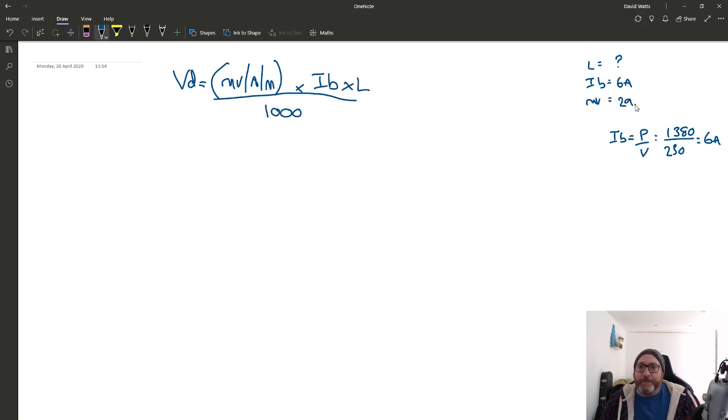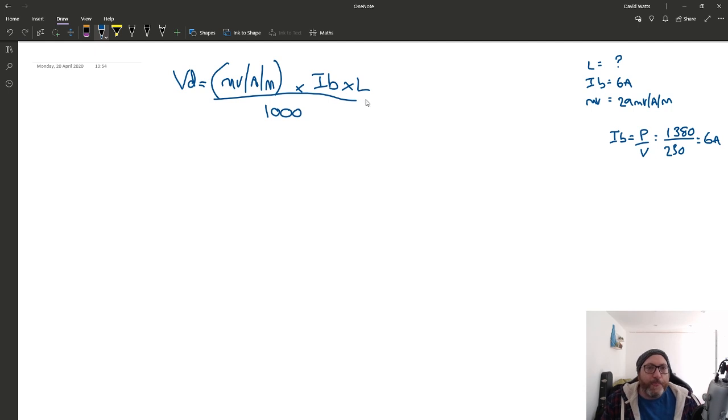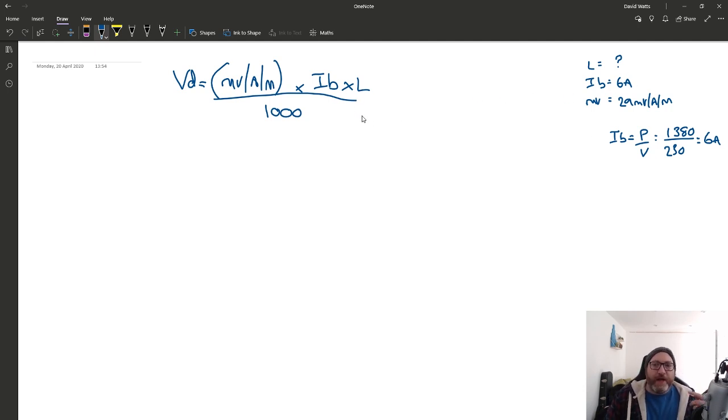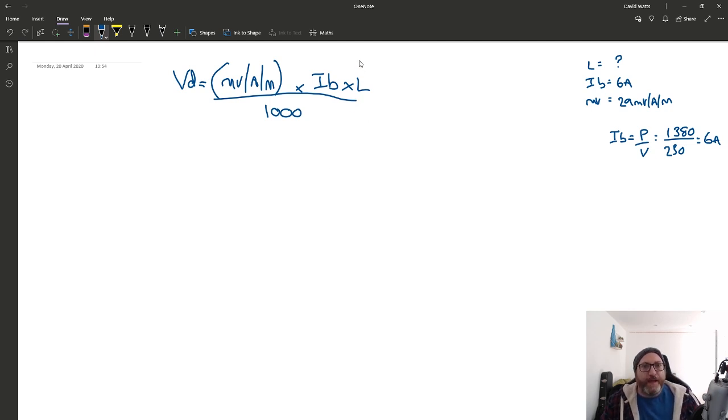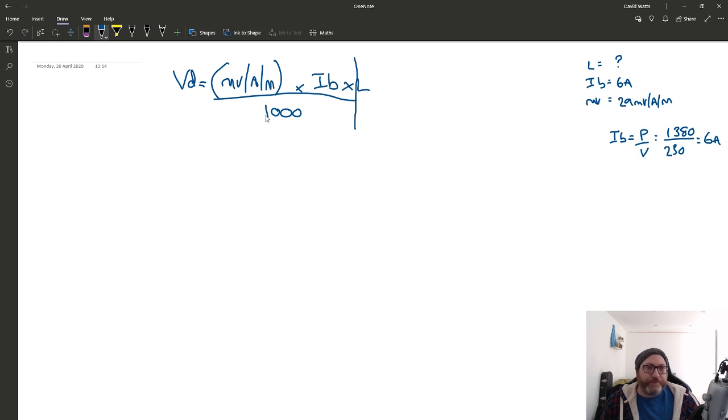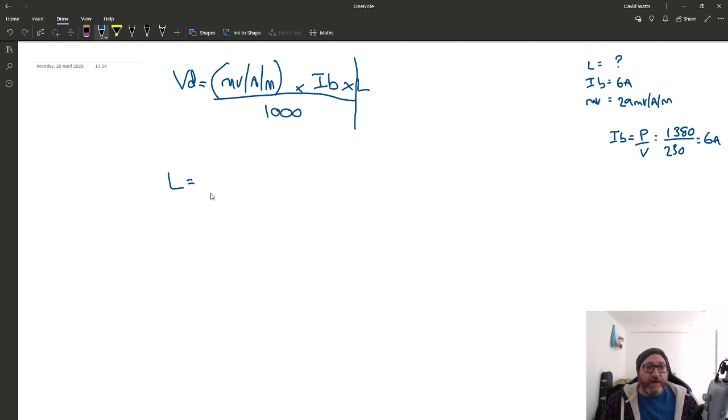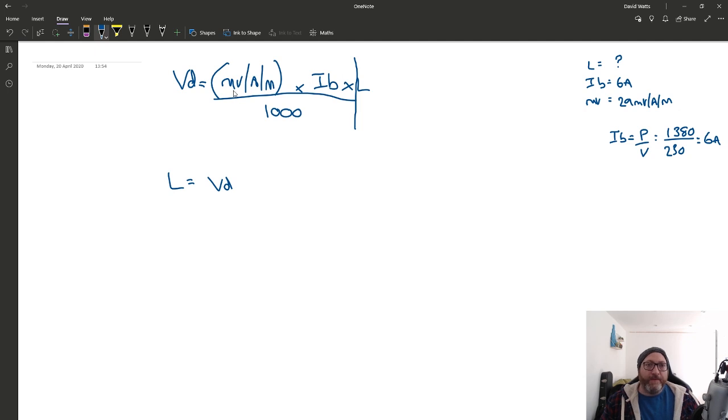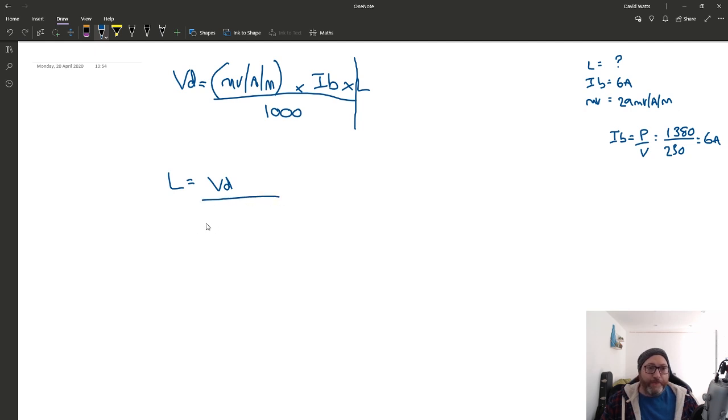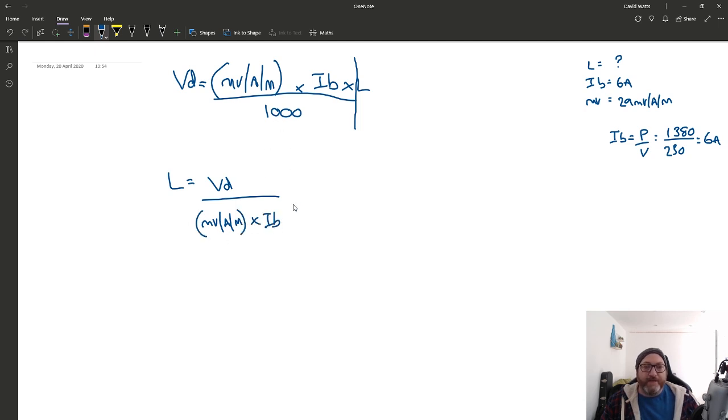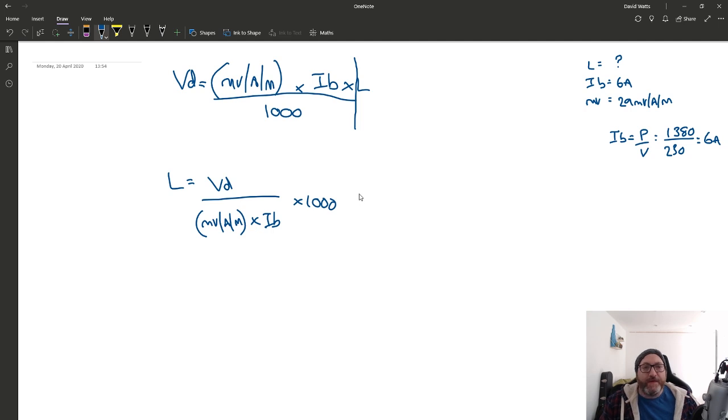Now we've got some information. Now we can start working things out. But first, the question is asking you what's length. So, this is where it talks about transposition of the formula. So, what you need to remember with that is take the thing that you want to take, the length here, and everything else the other side of that you need to bring this way, flipping it around. So, the volt drop is over there. It's already on the other side of the equals. So, in this case, length is equal to the volt drop. Now, millivolts per amp per meter times IB is multiplied by the length. So, we're actually going to divide that and then we divide by a thousand. So, we're going to multiply that like this.